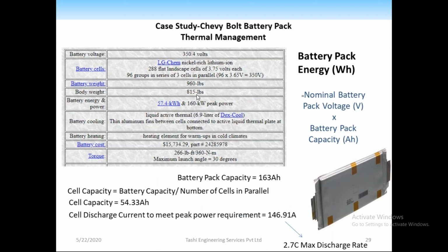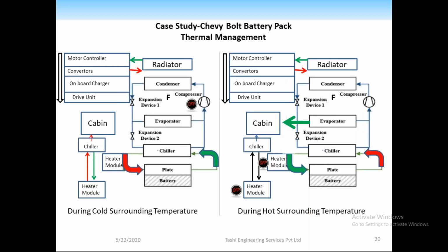This is the Chevy Bolt battery pack—the same slide we discussed, where the peak power is mentioned as 160 kilowatts. From that, we get a maximum of 146 amps that a single cell can draw. These are just basic calculations, which help me conclude that the maximum discharge rate in the Chevy Bolt will be 2.7C rate. Whatever thermal system I design should accommodate that design point, since that's the maximum design condition.